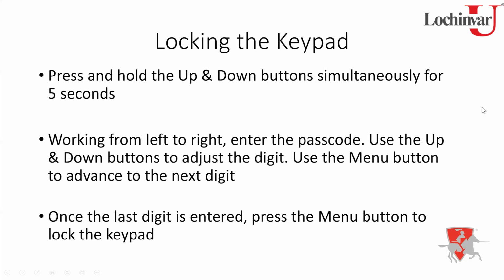To lock the keypad, you've got to press the up and down buttons simultaneously for 5 seconds. So use your 2 thumbs, 2 fingers, whatever, and hold those 2 buttons down for 5 seconds. At that point, it's going to bring up the lock keypad screen. That's going to give you 4 digits to work in. You're going to work from left to right. You're going to use your up and down buttons to adjust that first digit on the left side to whatever number you want, from 0 to 9. Press the menu button, and it moves you to the next digit. You're going to keep doing that until you get all 4 digits in. Once you get that 4th digit in, press that menu button. It's going to lock the keypad. It's going to flash up keypad lock in the display.